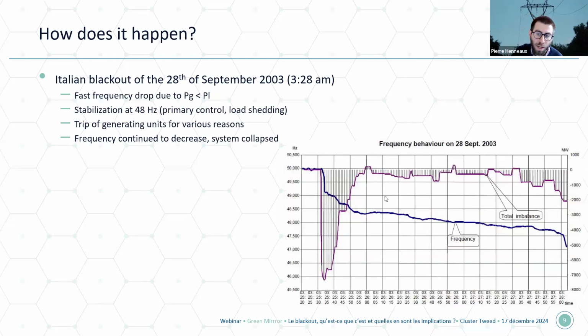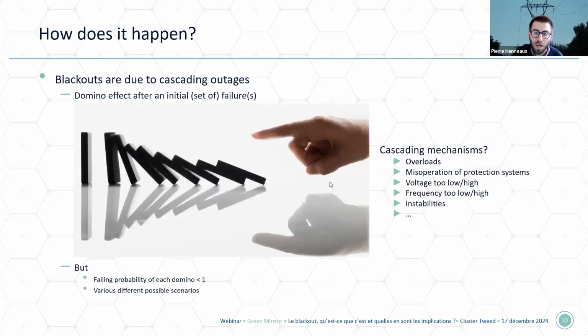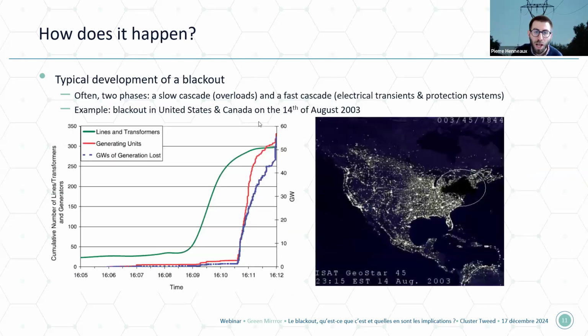which means that thousands of elements were disconnected in a few minutes. So you need to wait 24 minutes to have the second element disconnected, and then thousands of elements are disconnected in a few minutes. So you see that you have a slow cascade due to overloads, and then a fast cascade due to electrical transients and protection systems.